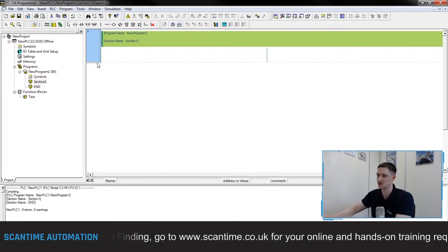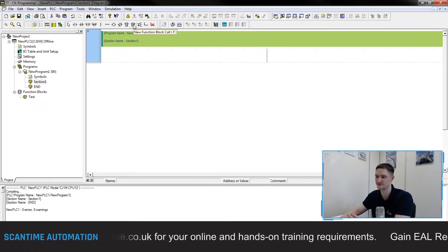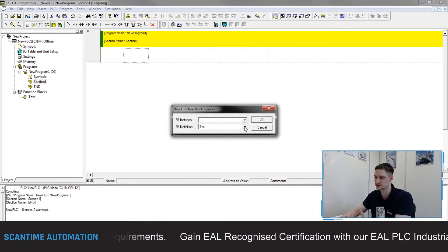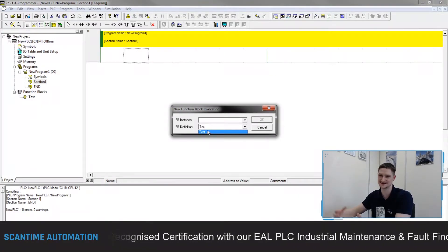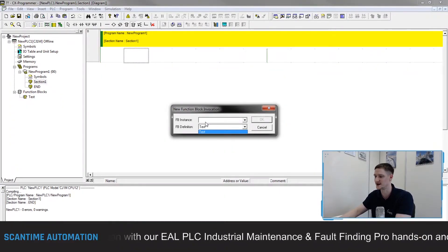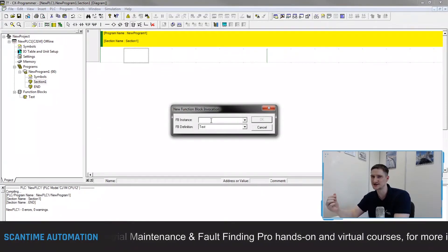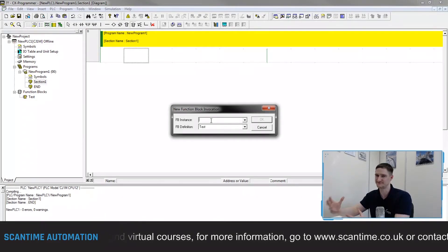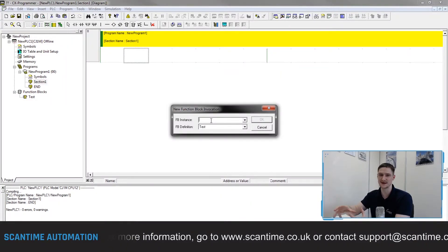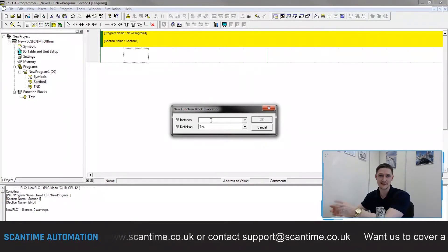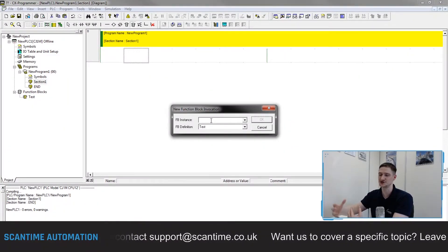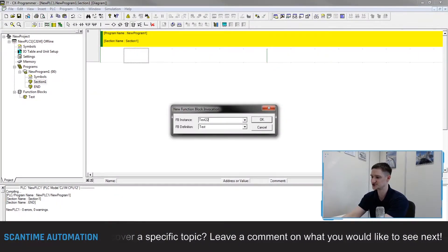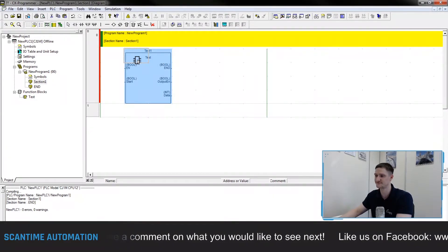When placing the function block call, it asks for the function block definition — I select 'test'. It then asks for an instance name. Think of this like an instance data block in a Siemens PLC — it's the memory area for that function block. This allows the PLC to create a memory structure, store information, and retrieve it on every scan, bypassing the duplication problem. I'll call this instance 'test1'.